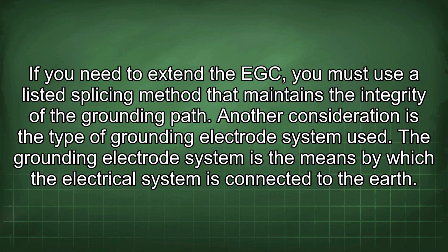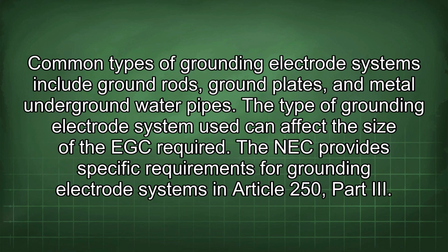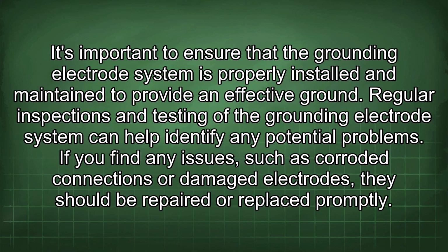The grounding electrode system is the means by which the electrical system is connected to the earth. Common types of grounding electrode systems include ground rods, ground plates, and metal underground water pipes. The type of grounding electrode system used can affect the size of the EGC required. The NEC provides specific requirements for grounding electrode systems in Article 250, Part III. It's important to ensure that the grounding electrode system is properly installed and maintained to provide an effective ground.